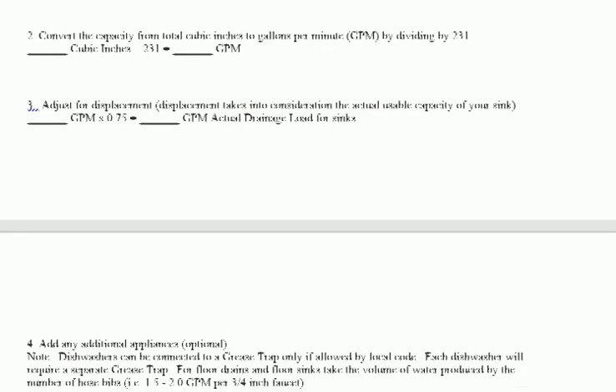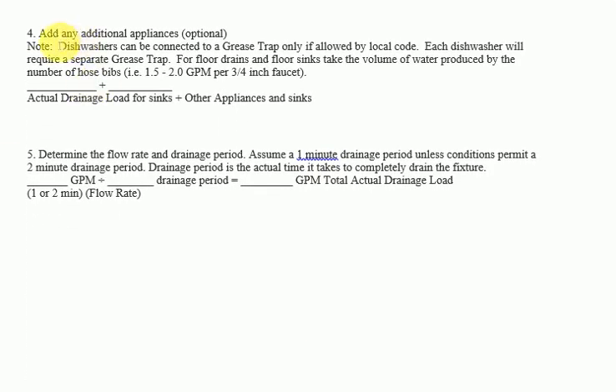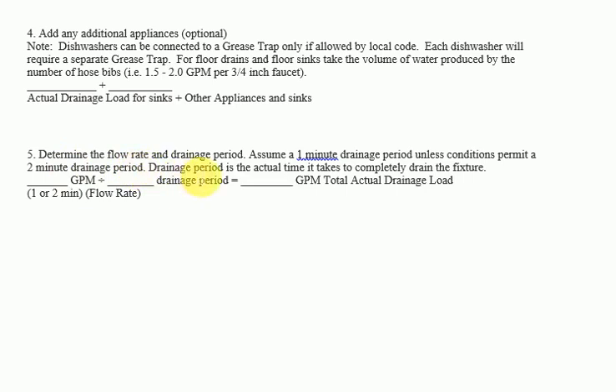Step 4 — Add any additional appliances. Note: dishwashers can be connected to a grease trap only if allowed by local code, and each dishwasher will require a separate grease trap. For floor drains and floor sinks, take the volume of water produced by the number of hose bibs — approximately 1.5 to 2.0 GPM per 3/4-inch faucet — and add to the actual drainage load for sinks.